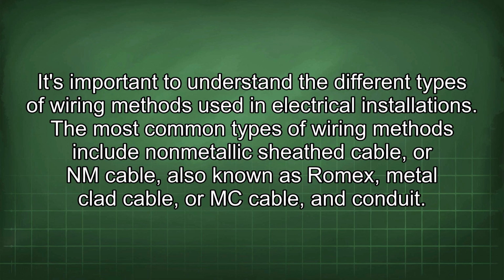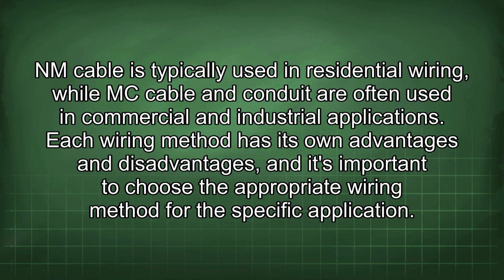It's important to understand the different types of wiring methods used in electrical installations. The most common types of wiring methods include non-metallic sheath cable, or NM cable, also known as Romex, metal clad cable, or MC cable, and conduit. NM cable is typically used in residential wiring, while MC cable and conduit are often used in commercial and industrial applications.